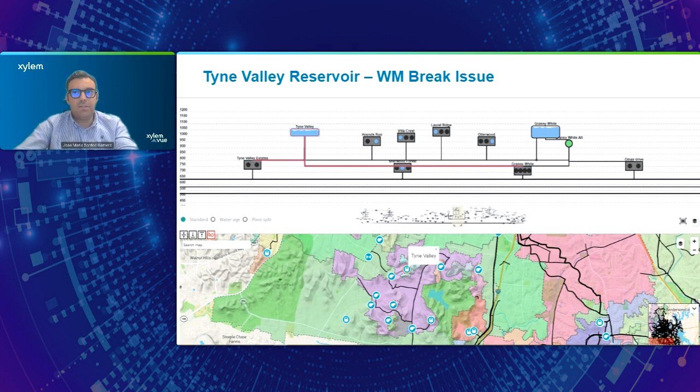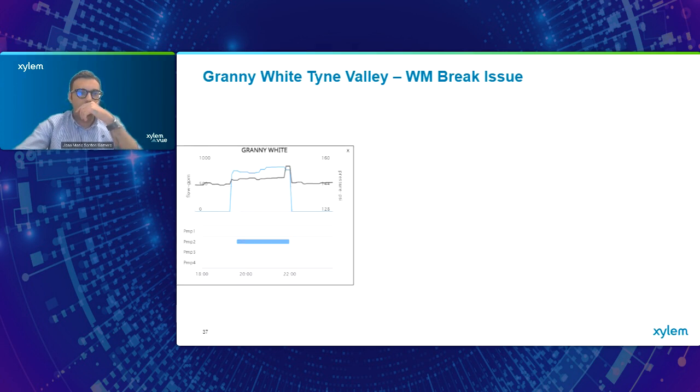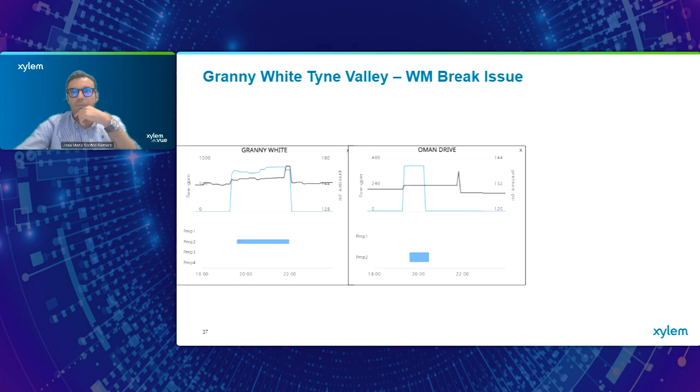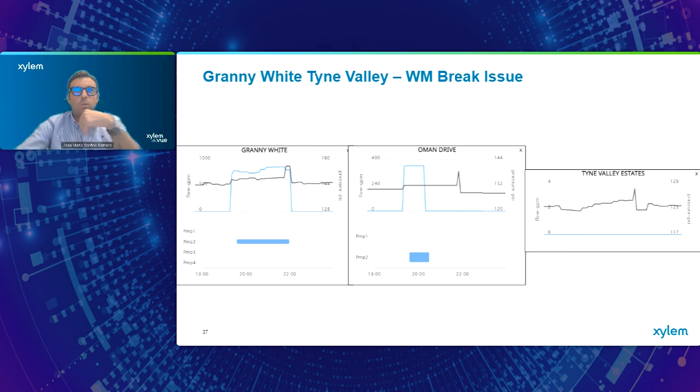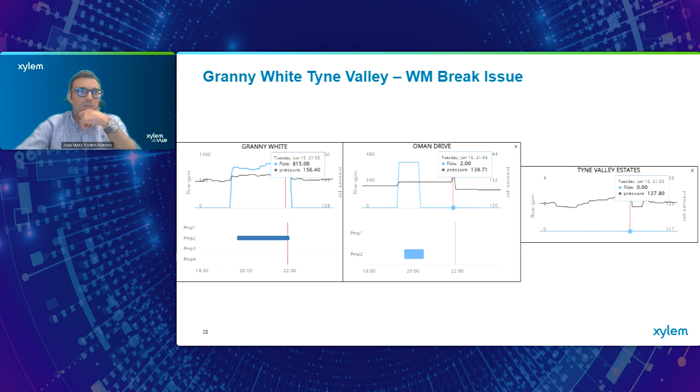What happened in this case was that, putting together all the information collected at the pump stations, there may be something that jumps directly at your eyes. Again, you're looking at June 15 from 6 p.m. to midnight. If you pay attention, you can see that all the pump stations were getting a spike at the same time, which is 9:55 of the same day. You can see that here, and there.